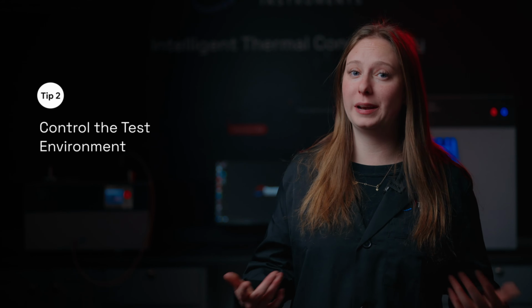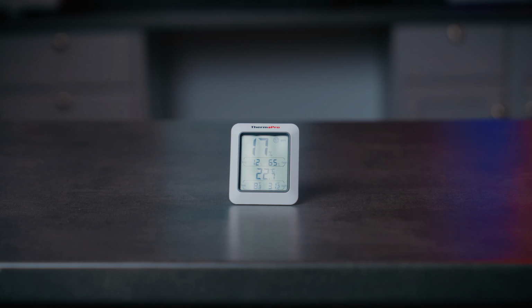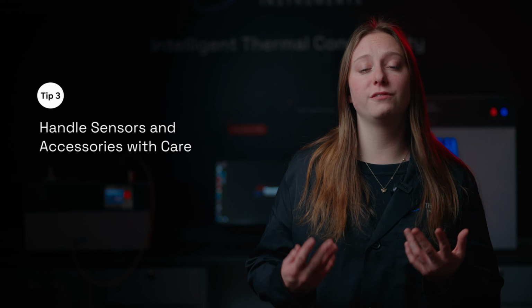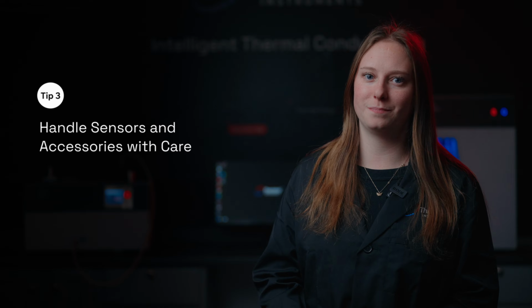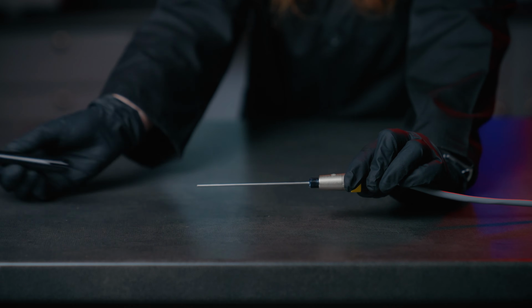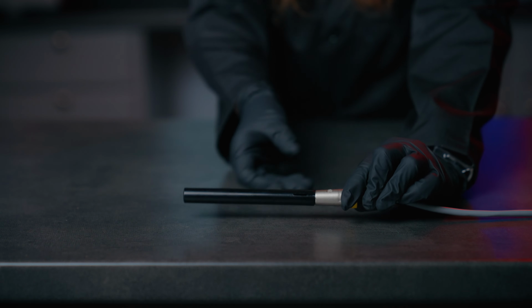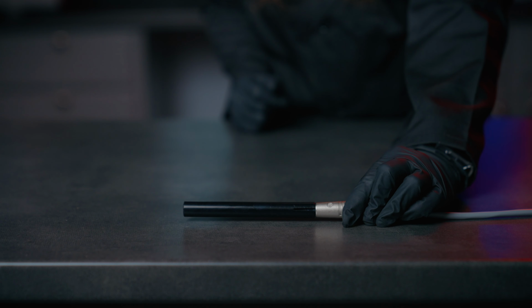Ambient temperature, humidity, and airflow all can influence sensitive thermal measurements. Keeping your lab environment stable reduces noise and improves long-term measurement consistency. If environmental conditions change significantly, your calibration may no longer be valid and recalibration may be required. Sensors and accessories are often the most vulnerable components of a thermal testing system. Avoid excessive bending, pulling, or contamination, and inspect components regularly for wear or damage. Proper handling helps preserve calibration integrity and extends your instrument's lifespan.